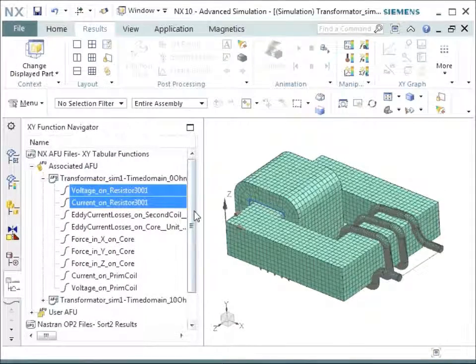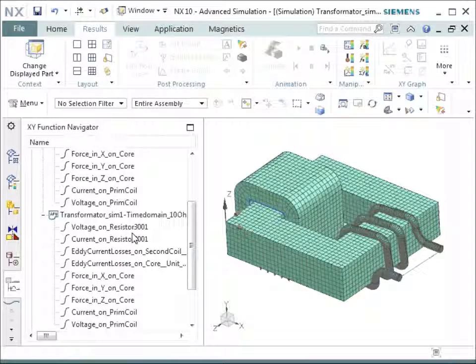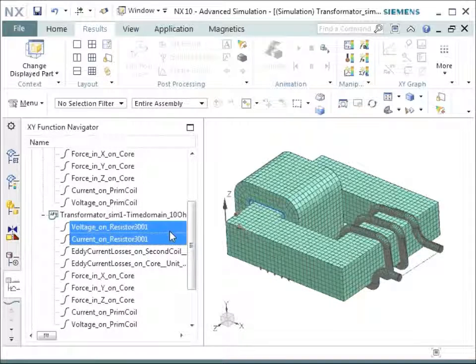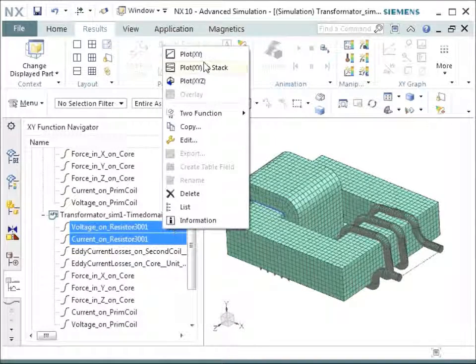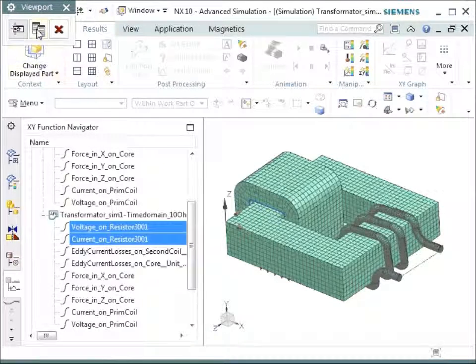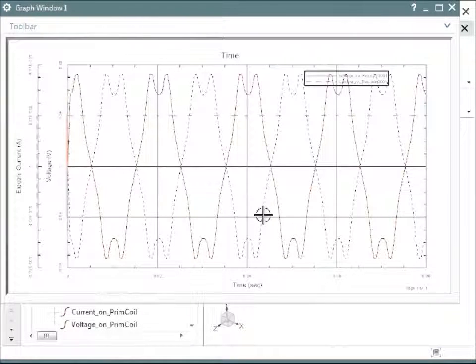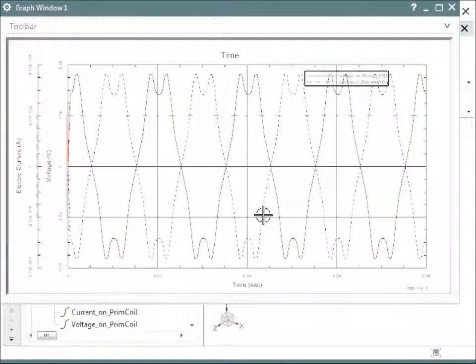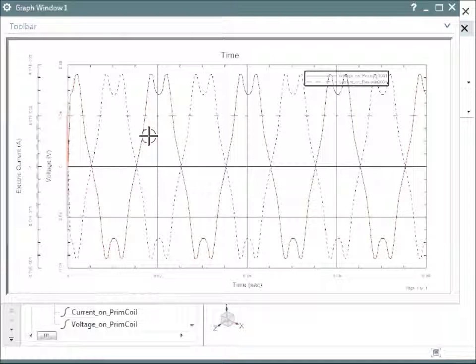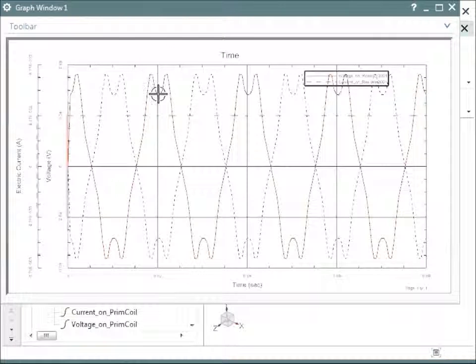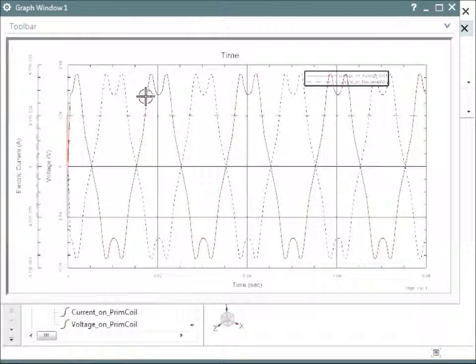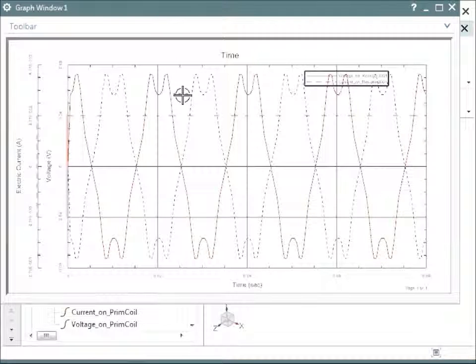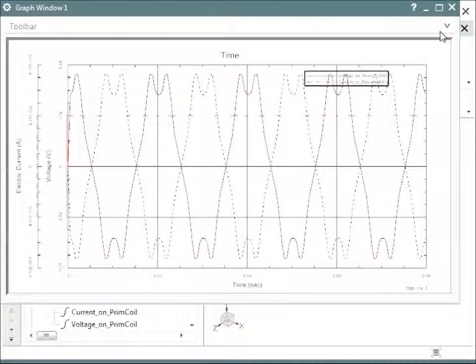Let's compare this with the loaded case. So let's open the same two curves in the case of a loaded transformer. So in this case, it is completely different. We see that current and voltage are phase shifted by 90 degrees. And we see that the sinuous behavior is changed by a non-linear type. And this non-linear behavior comes from the saturation effects that we have applied to the analysis. So it's a very accurate analysis.